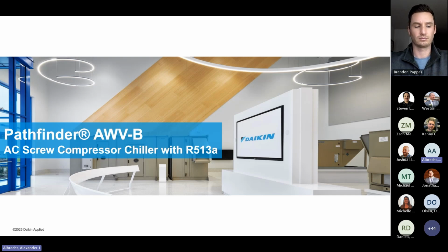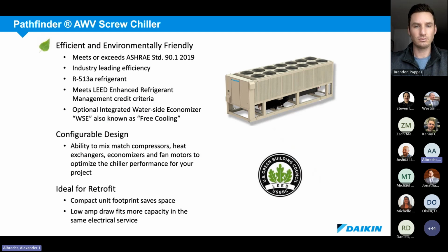So starting with our Pathfinder, again, this is our air-cooled screw chiller from roughly 100 up to 550 tons of capacity, designed for high efficiency. In fact, we are an industry leader in efficiency, exceeding ASHRAE 90.1, currently with R513A refrigerant, exceeds LEED criteria, optional water side economizer for free cooling, as well as integrated pump option. Some of the strengths that we have are configurable design, able to mix and match critical components to be optimized for target specifications, as well as ideal for retrofit with advanced efficiency, very low footprint, as well as able to meet all current existing building MCA, MOCP requirements.